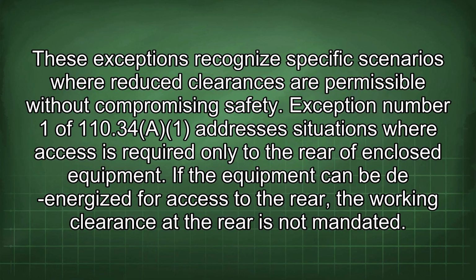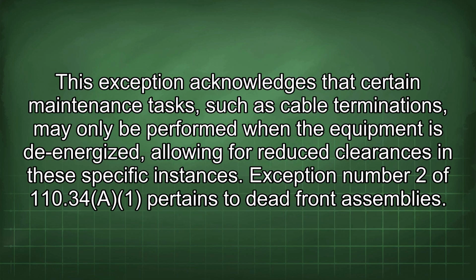Exception number 1 of 110.34(A) addresses situations where access is required only to the rear of enclosed equipment. If the equipment can be de-energized for access to the rear, the working clearance at the rear is not mandated. This exception acknowledges that certain maintenance tasks, such as cable terminations, may only be performed when the equipment is de-energized, allowing for reduced clearances in these specific instances.